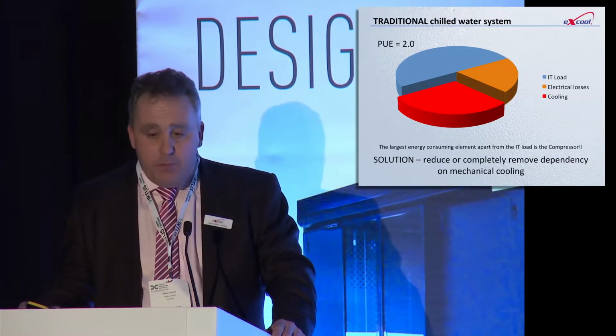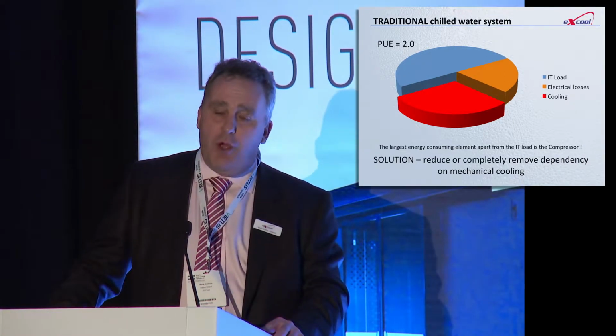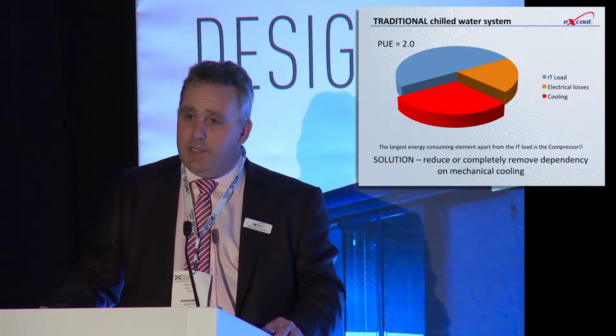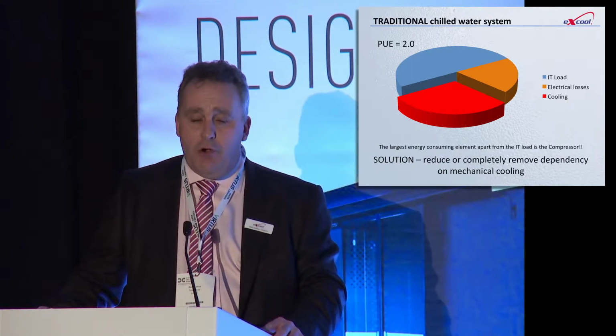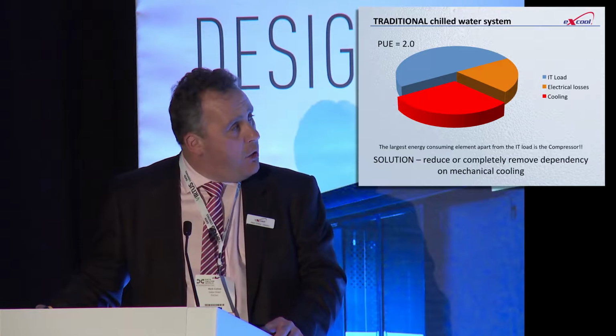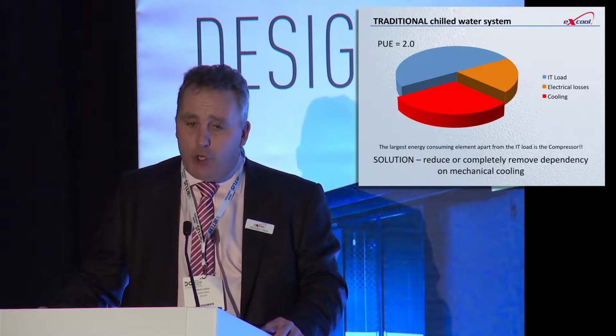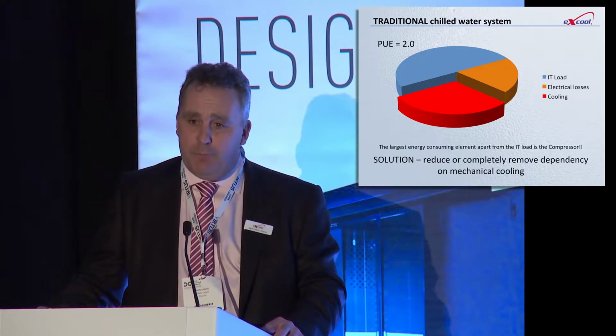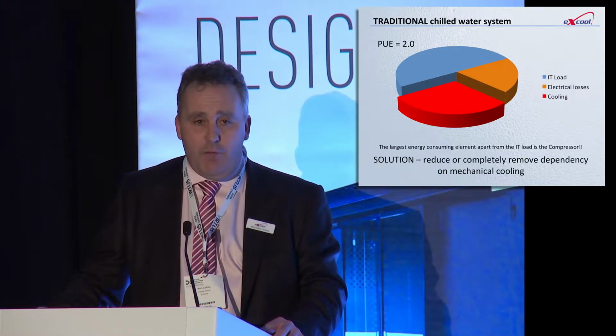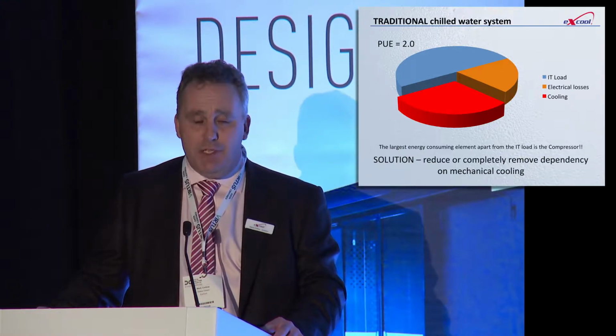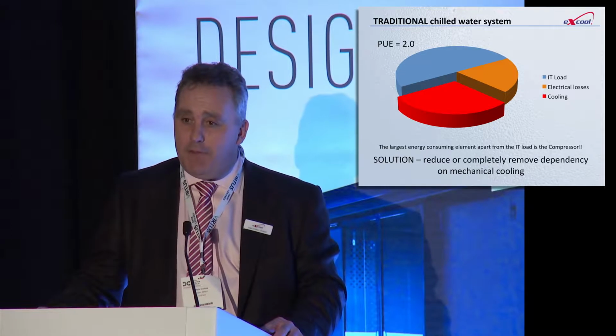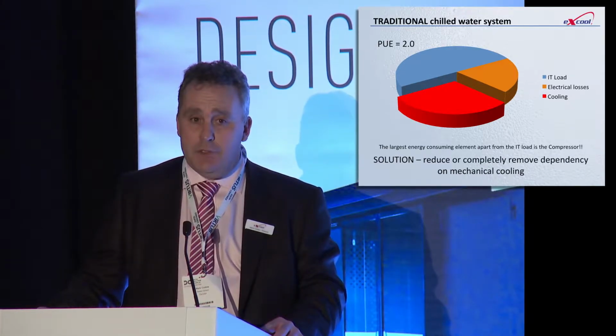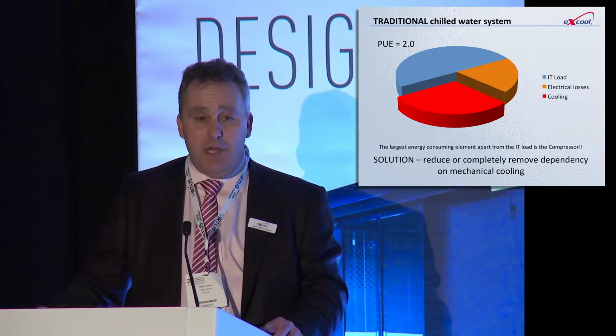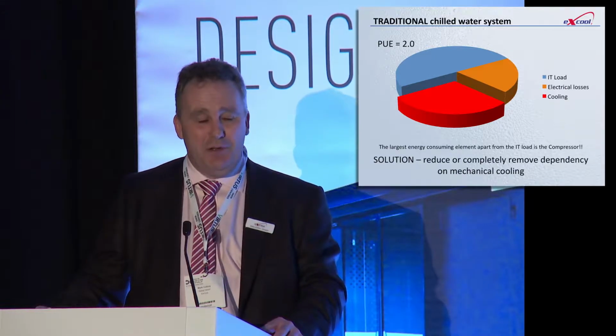So just to begin with where we're at right now, typical PUEs in the data center market are around about 2. And of that, around about a quarter is built up of cooling. So for every kilowatt of power you deliver to the space, you're using about half a kilowatt just to cool it down. So your IT power needs half as much again to cool it down.